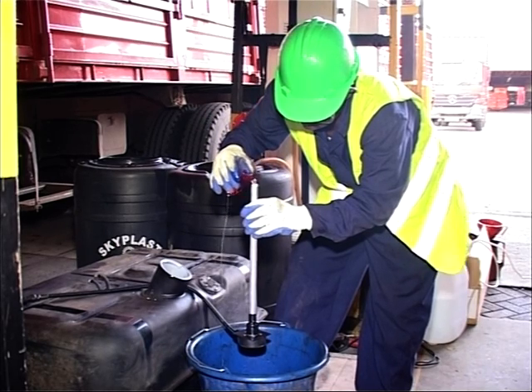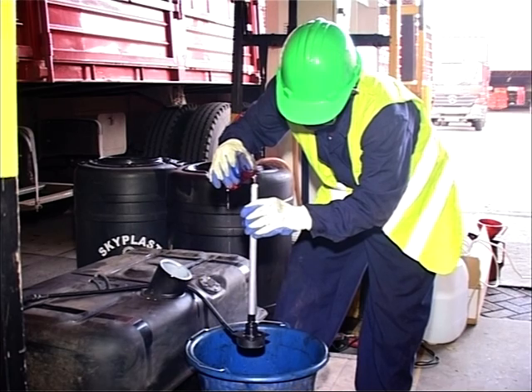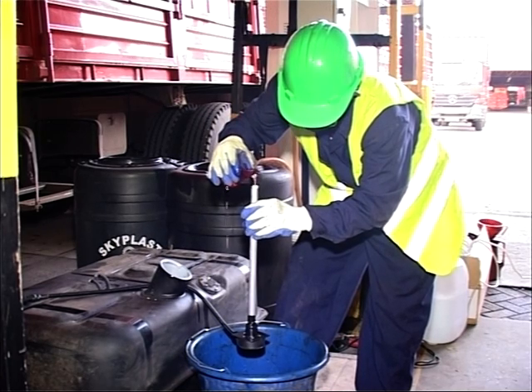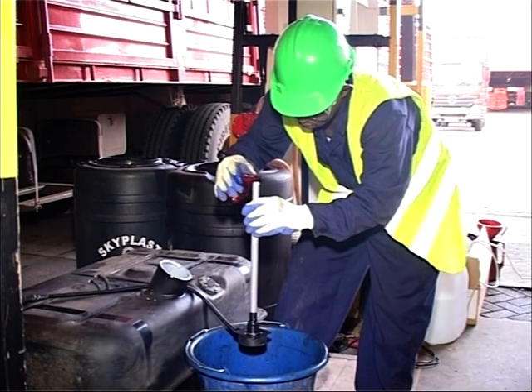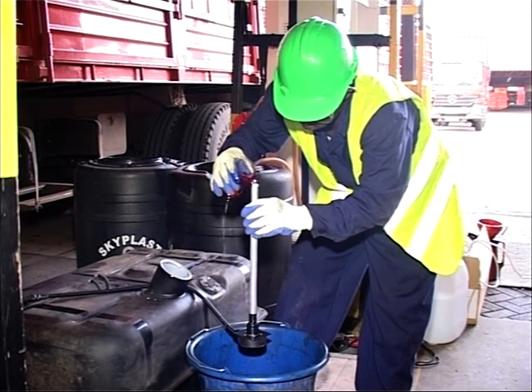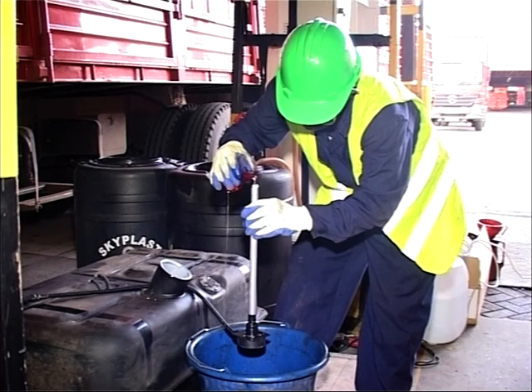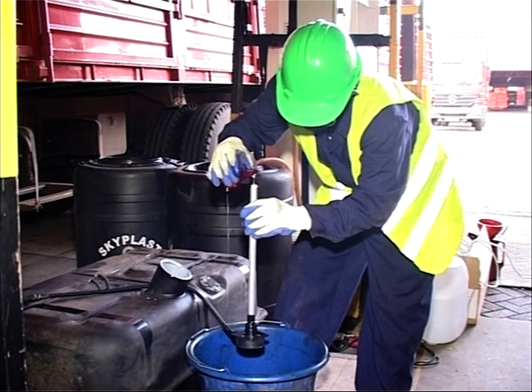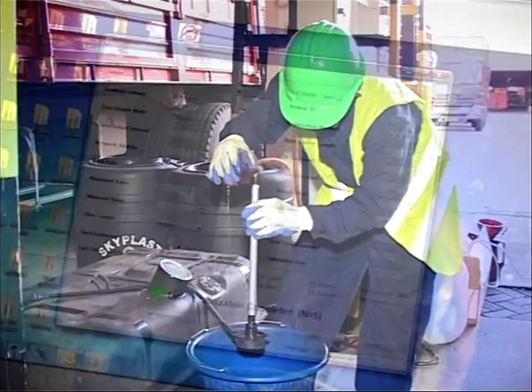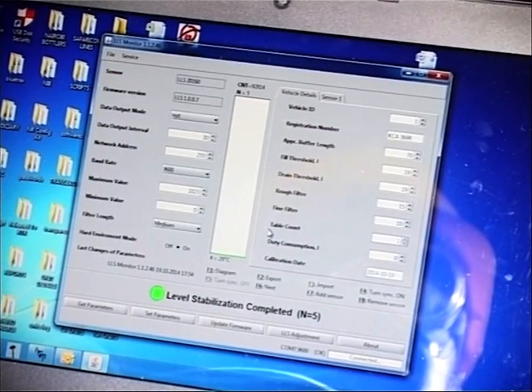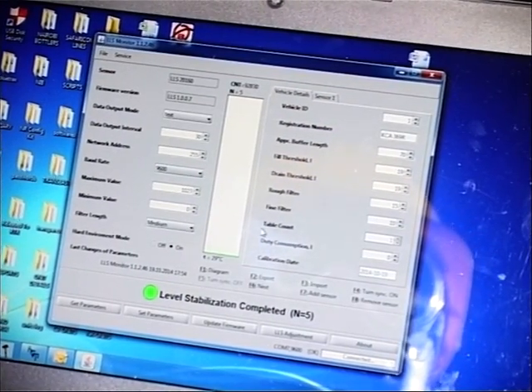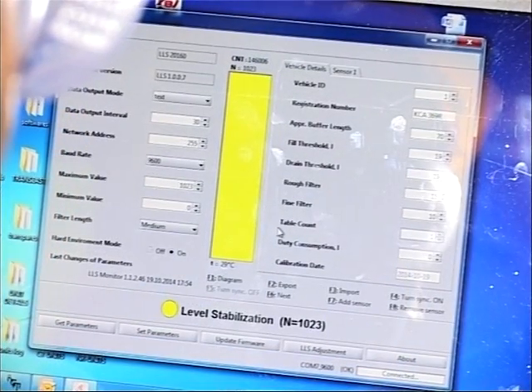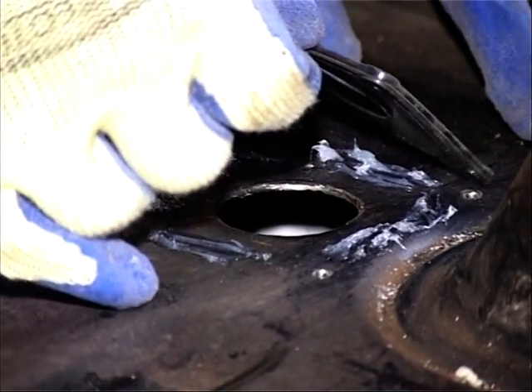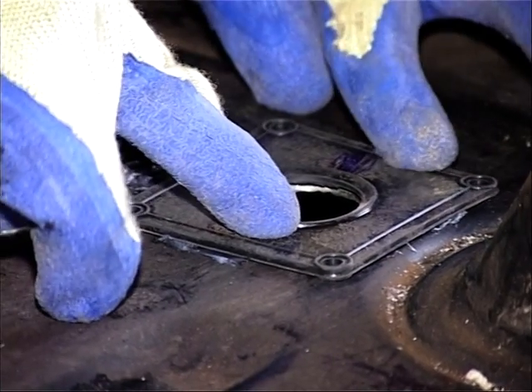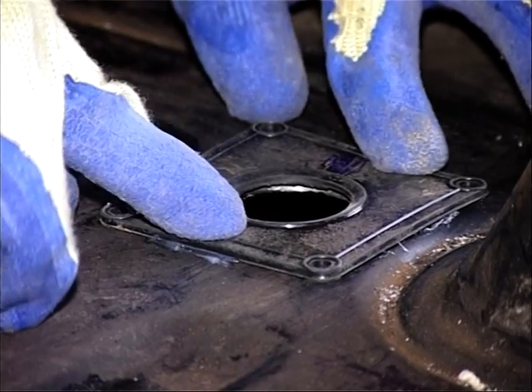In an inverted position, the sensor has perforations at the base, so the base is sealed up. The reason being the level sensor has to be calibrated using the type of fluid that is going to be applied on. And in this case, we're using diesel fuel. Here we get to calibrate for empty and set the values, and also full, where we also set the values. Here we use silicon sealant to prevent any future fuel leaks from the tank through the sensor.